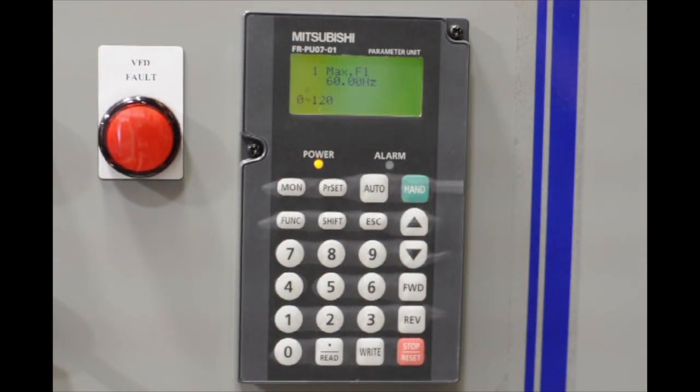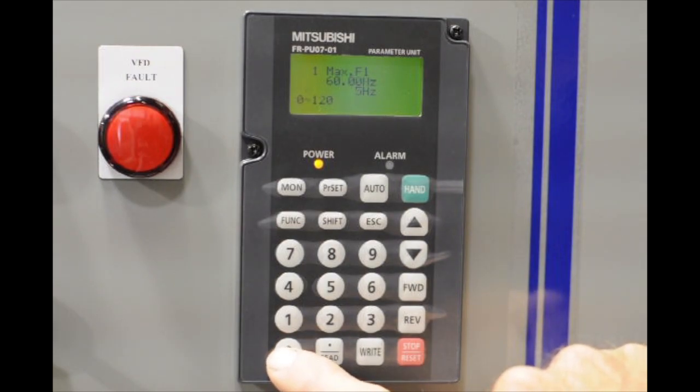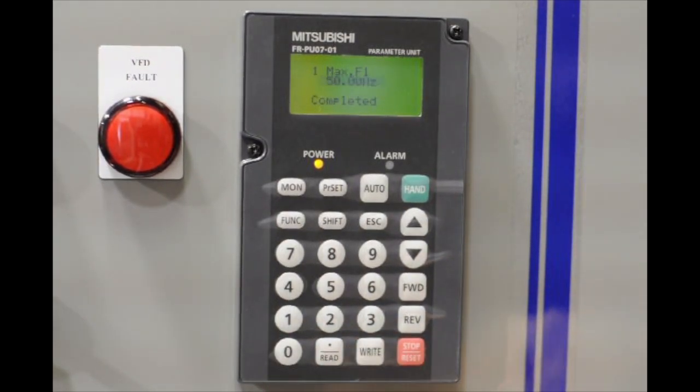This will show you what the parameter number is, what parameter title is, and the actual setting value. This parameter is set for 60 hertz, which is our desired setting, but for this illustration, I'm going to go ahead and change it to 50 hertz. We're going to type in 50, and we're going to hit write.